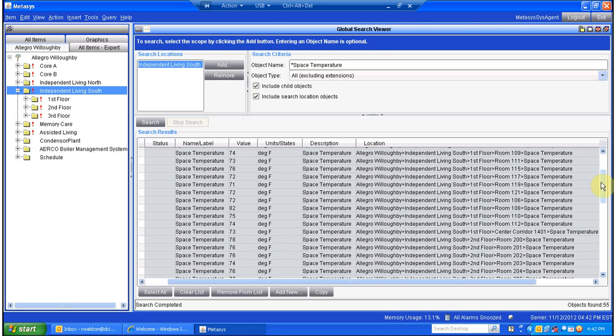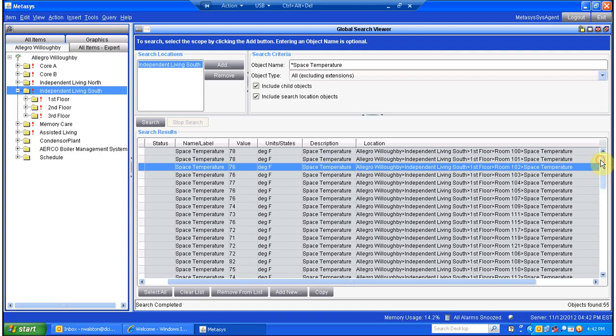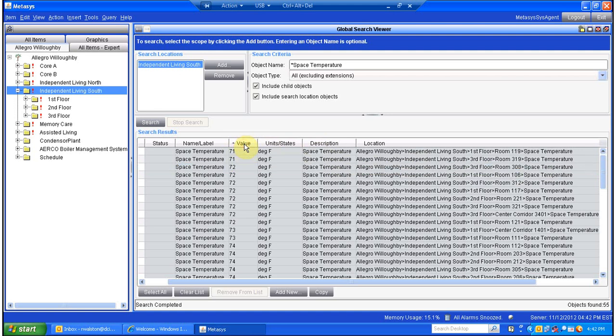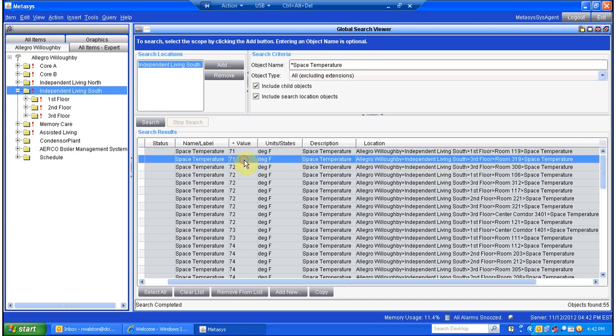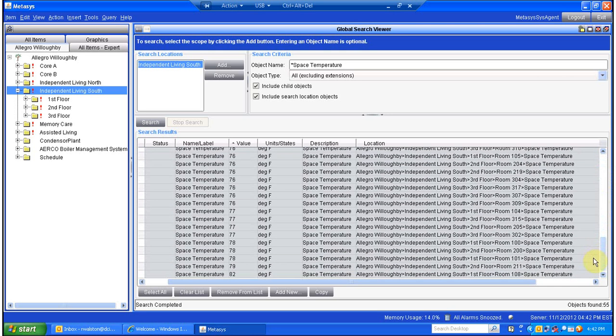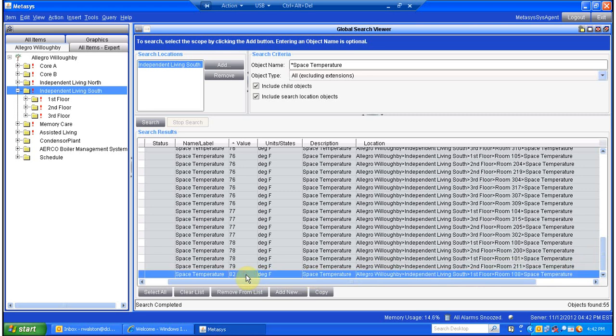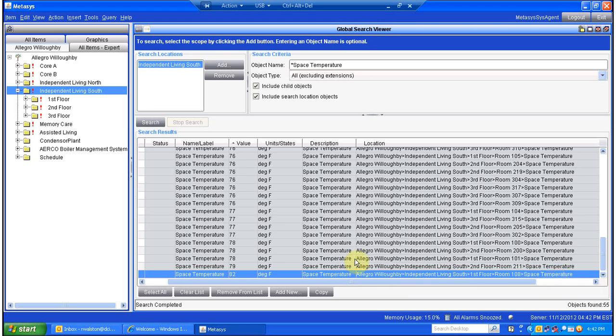Now we can start looking down through the list and seeing the temperatures in individual rooms. But let's say we were looking to see who has the highest room temperature and who has the lowest. We can actually go by value — click on this column header and sort it by value. Room 119 is 71, and also 319 is 71, so we can see they've got their thermostats jacked down. Also we can see at the bottom that room 108 seems to like it at 82 degrees — either that or there is something wrong with their air conditioner.